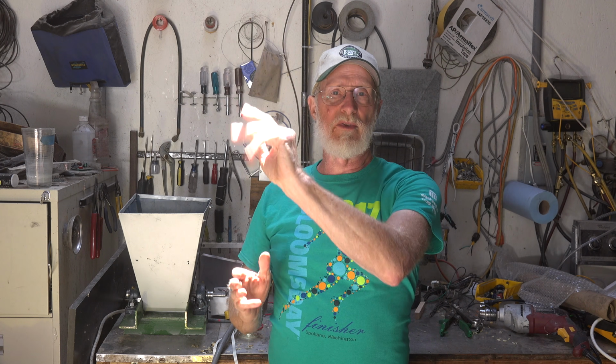Well, then we have a problem there, because the higher it is, the harder it is to get the oil to come back completely. And so sometimes we'll put traps in the line, a little trap like that, so that the gaseous refrigerant has to bubble through the oil and pull it back up with it. There's all sorts of things like that we sometimes do.